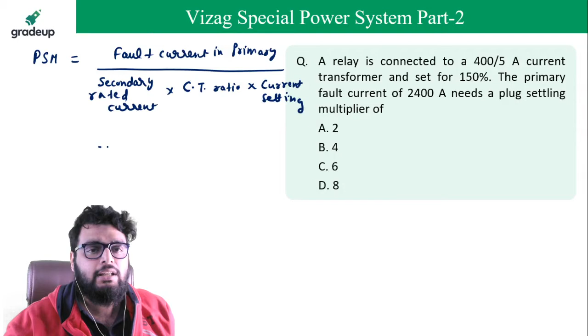So in this question, what is the fault current in primary? It is 2400, divided by the secondary rated current. See, in this question the secondary rated current is not given. If the secondary rated current is not given, then take the secondary of the current transformer ratio as the secondary rated current. Let me repeat again. If in the question the secondary rated current is not given, then take the secondary of the current transformer ratio as the secondary rated current. Multiply by CT ratio, which is 400 divided by 5, multiply by current setting, which is 150%, so multiply by 1.5.